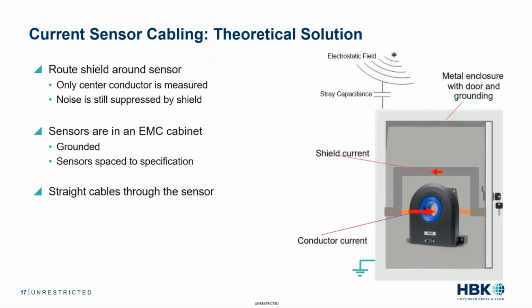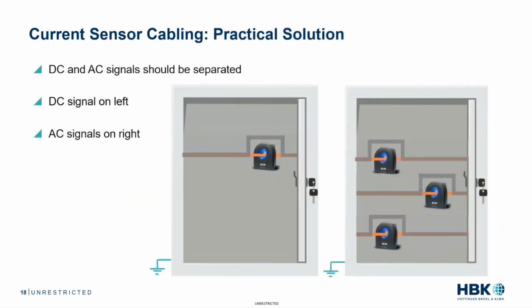Basically, routing the shield around the sensor and ideally placing the entire CT in this configuration of measurement within a Faraday cage-like box here, and only place the center conductor through the CT, and then the shield around the CT. Here, noise is still suppressed by the shield, and the sensors are in an EMC cabinet. It's grounded, and the sensors are spaced to specification. So ideally, you would want to have your DC signals in one cabinet, and then your AC signals in their own cabinet, separated from AC and DC. So that would be kind of a practical solution there.